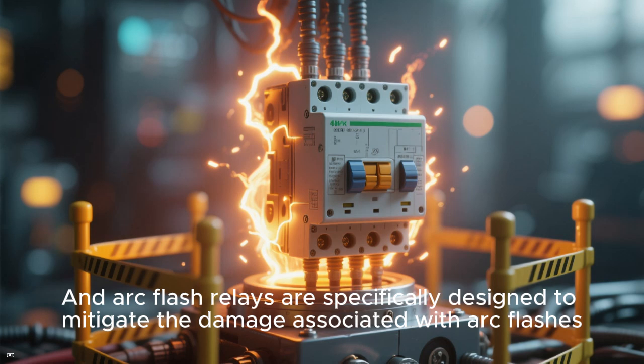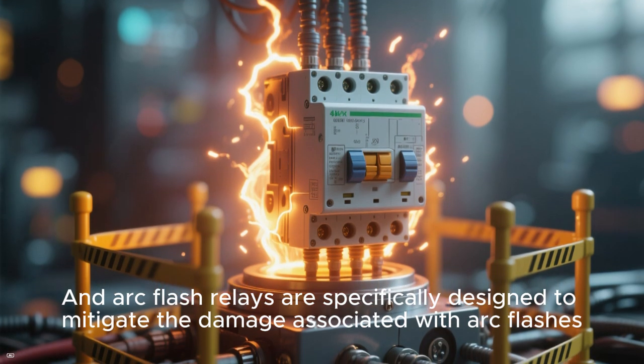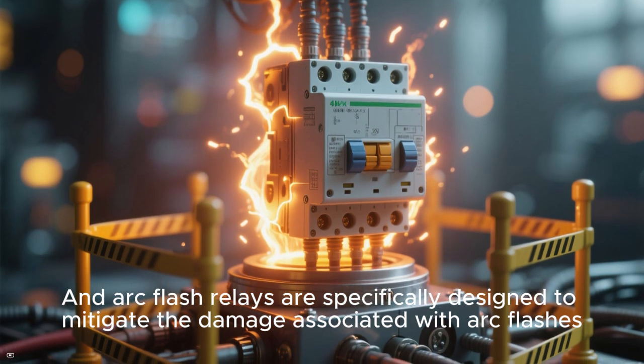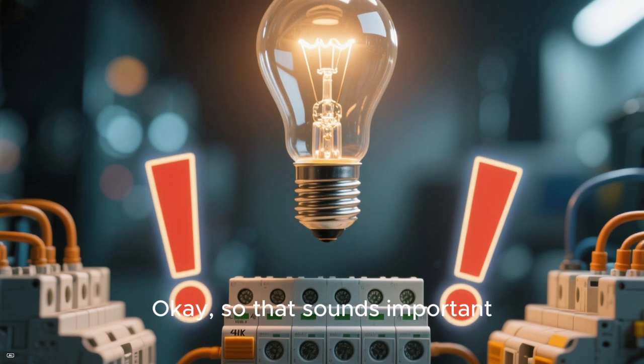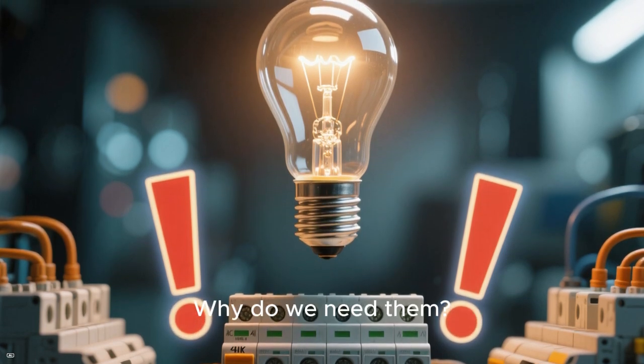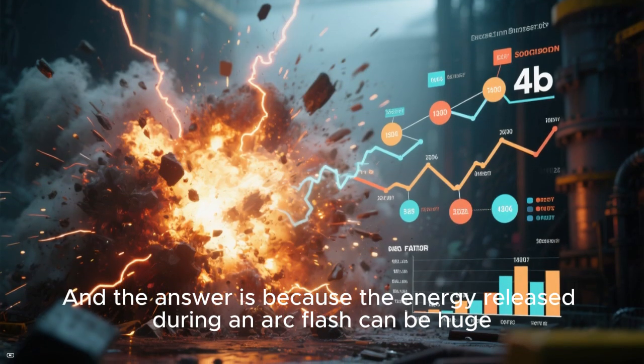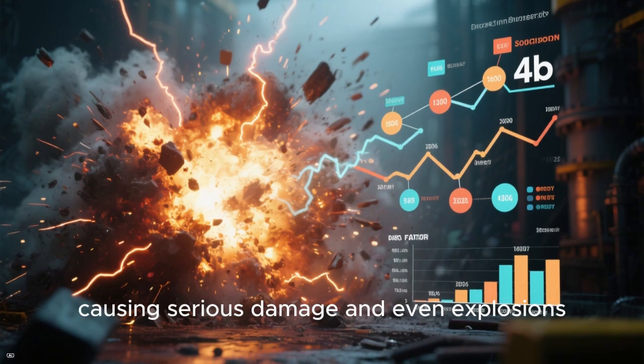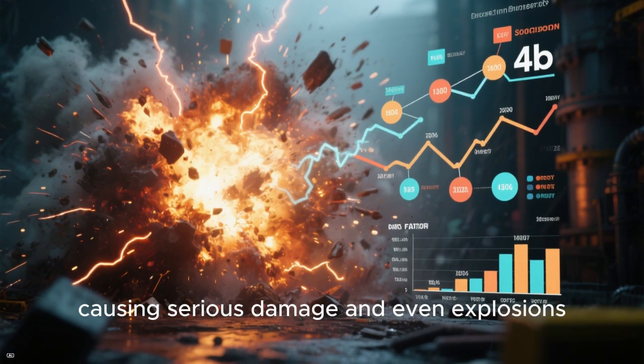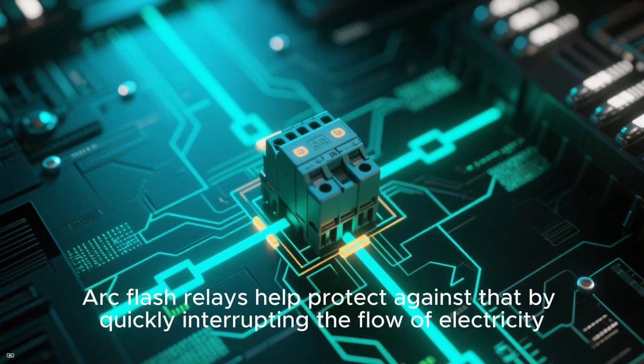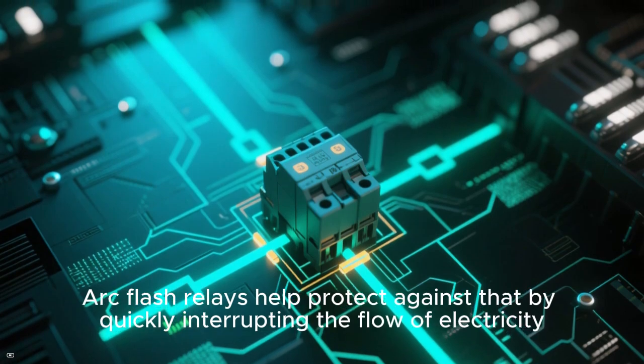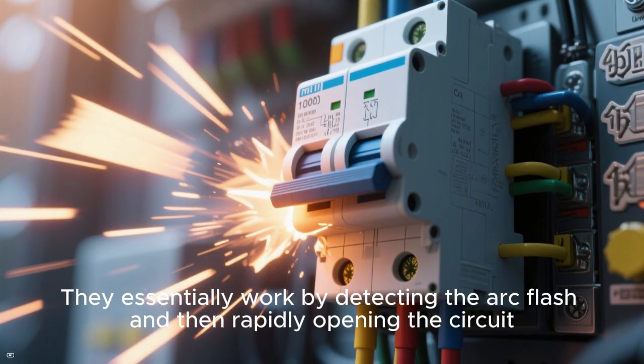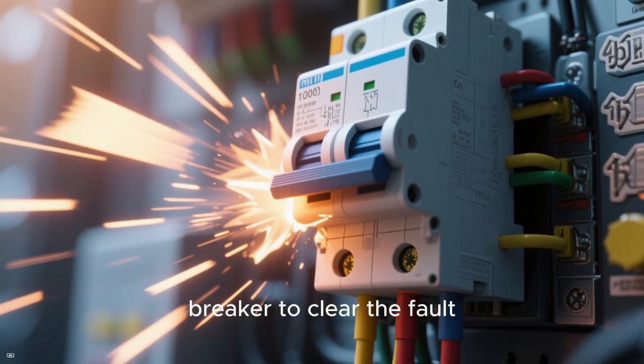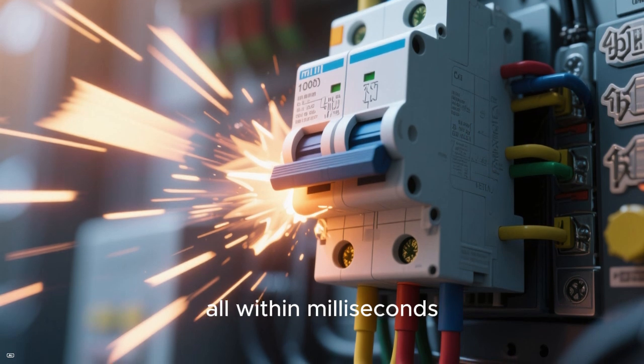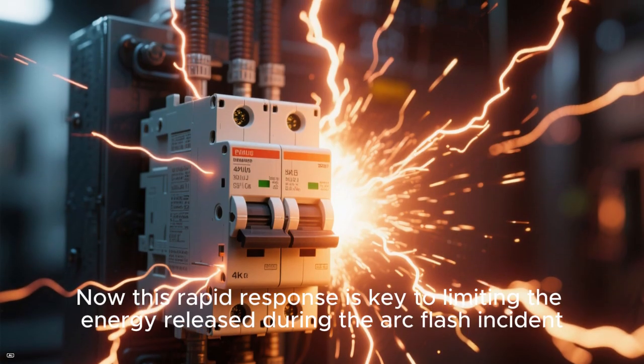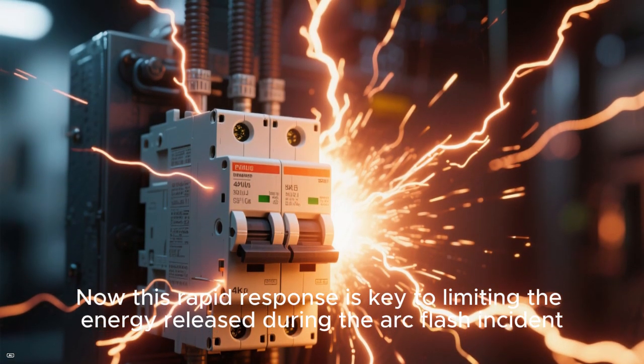And arc flash relays are specifically designed to mitigate the damage associated with arc flashes. Okay, so that sounds important. Why do we need them? The answer is because the energy released during an arc flash can be huge, causing serious damage and even explosions. Arc flash relays help protect against that by quickly interrupting the flow of electricity. They essentially work by detecting the arc flash and then rapidly opening the circuit breaker to clear the fault, all within milliseconds. Now, this rapid response is key to limiting the energy released during the arc flash incident.